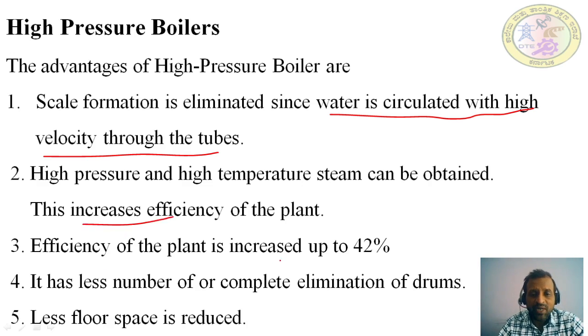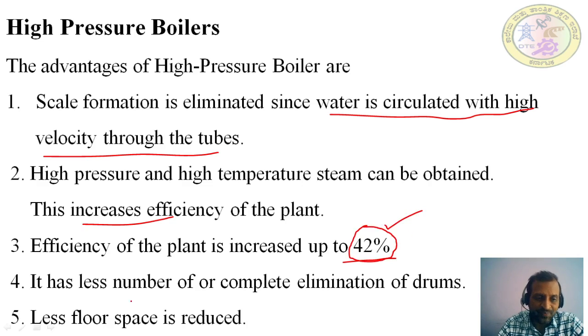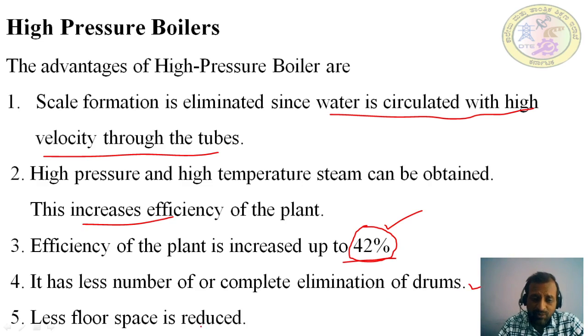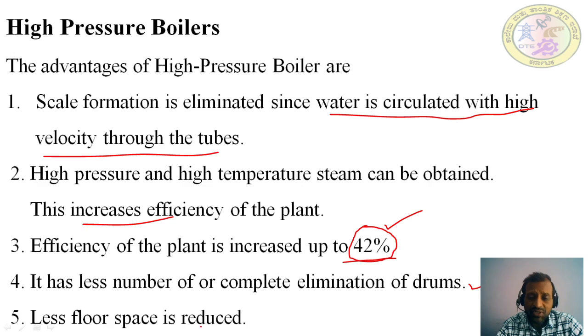The efficiency of the plant is increased up to 42% compared to low pressure boilers. There is also less number of drums or complete elimination of drums. Whenever steam is generated directly, you can use it immediately for your applications — such fast steam generation means you do not need to store steam in a drum, so the drum can be eliminated in high pressure boilers.